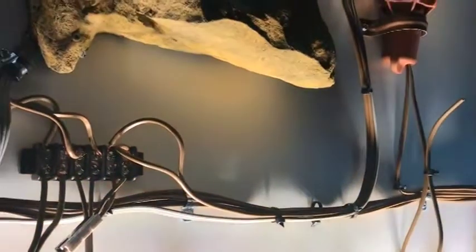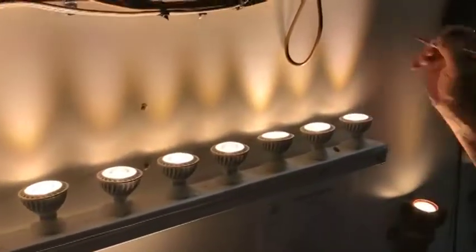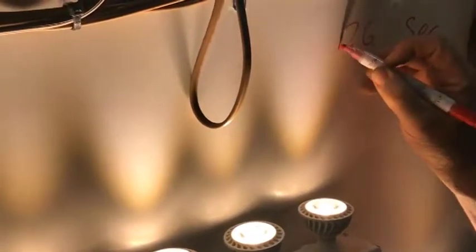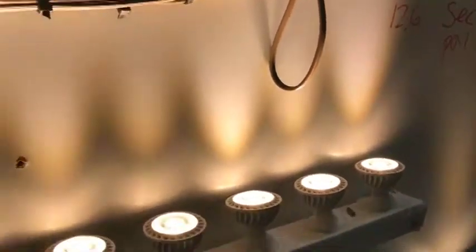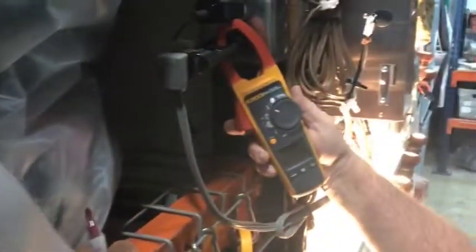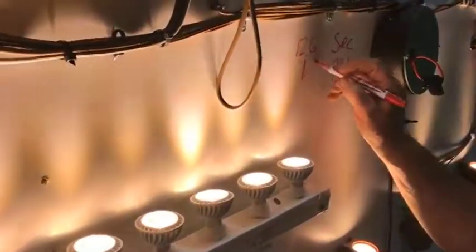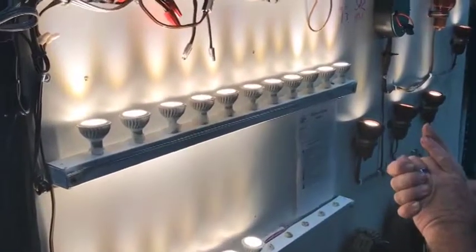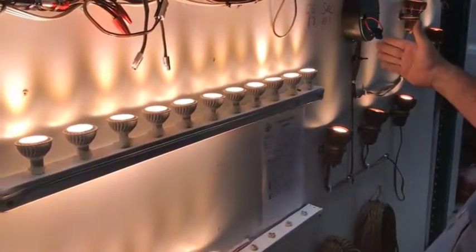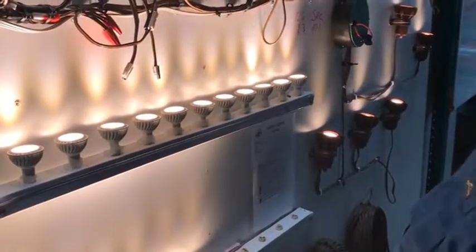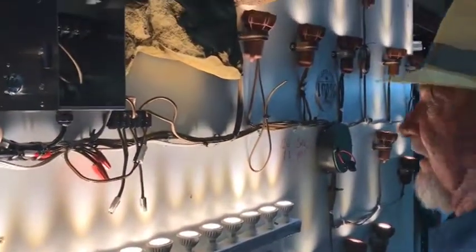And on the secondary, I have 12.6 amps. Okay, I'm gonna write this down so we do not forget. Secondary, 12.6. Now we're going to check the primary. Come on over here to the primary. I have 1.3. 1.3 on the primary. All right, so now we've got 12.6 on the secondary, 1.3 amps on the primary. And now what I want to do is disconnect it.